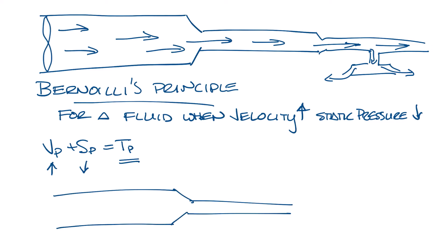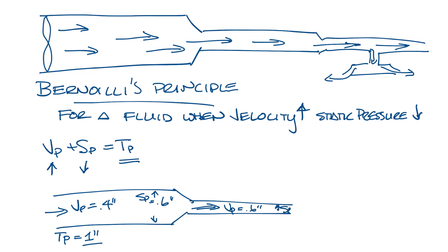So if we had a piece of ductwork, and let's say it has one inch total pressure, and that is made up of 0.4 inches velocity pressure and 0.6 inches static pressure, then let's reduce it to a smaller diameter ductwork. But because the air is moving through a smaller ductwork, it speeds up, so maybe now your velocity pressure is 0.6 inches and your static pressure is 0.4 inches.